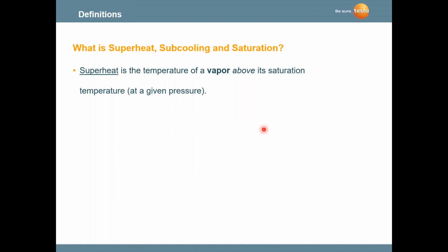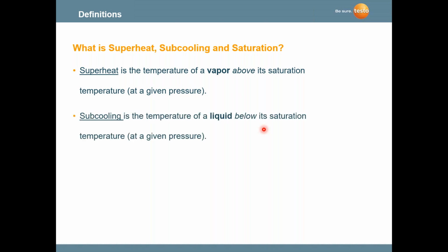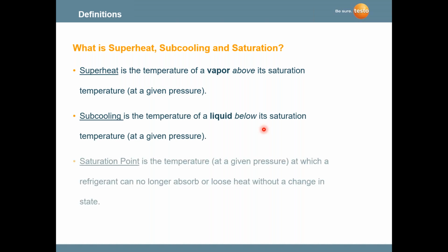So what is superheat? Well, we talked about it a little bit already. Superheat is the temperature of the vapor above the saturation temperature. Subcooling is the temperature of the liquid below the saturation temperature. And the saturation point, or the point at which we see a change of state, is where the refrigerant can no longer absorb or lose heat without changing that state.